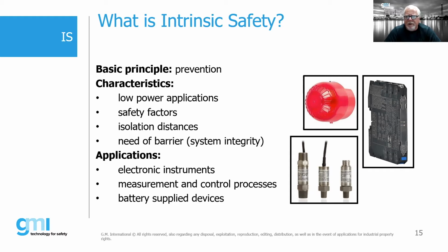There are safety factors built in. So when we actually get into the design of IS systems, we have safety factors that are built in. There's also a requirement for isolation distances between IS and IS, and also IS and non-IS. And of course, as we mentioned, we also need that barrier. The applications are pretty much your electronic instruments, your measurement and control processes, your battery supply devices, your 4 to 20 milliamp transmitters, thermocouples, solenoid valves, all of the instrumentation and measuring devices that we typically find in a process facility. That is really ideal for the use of intrinsic safety.